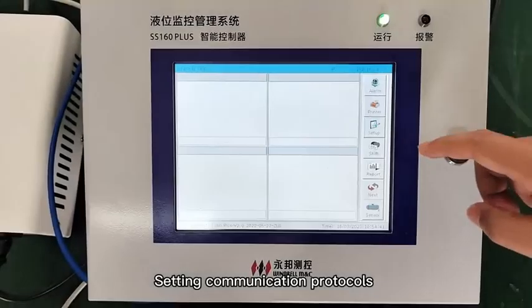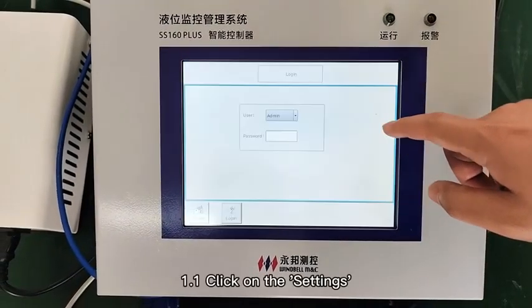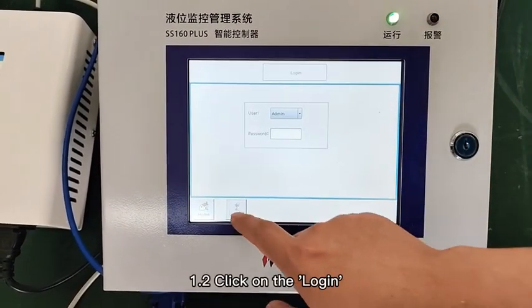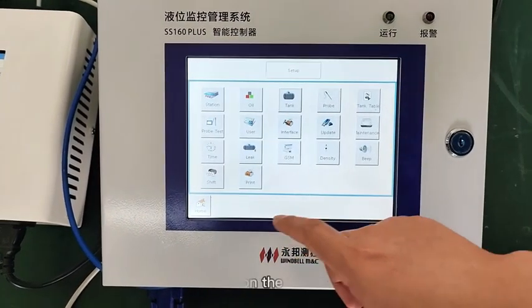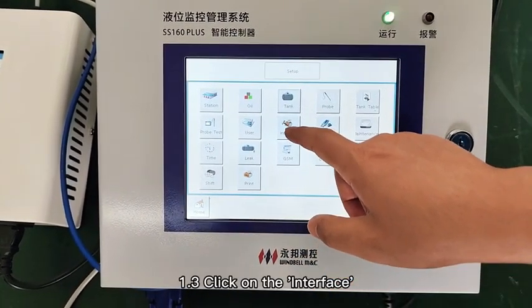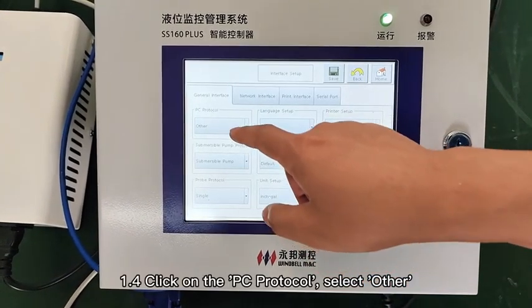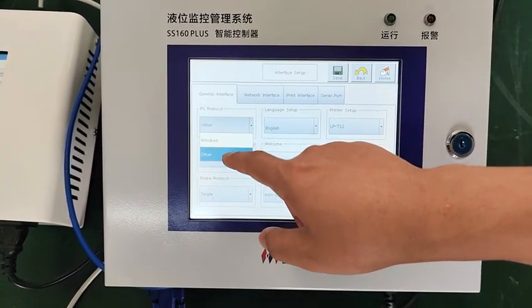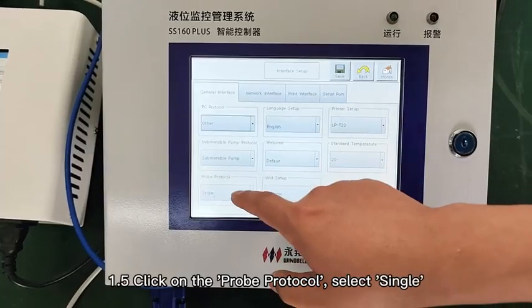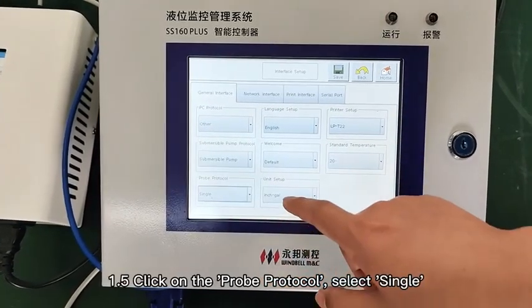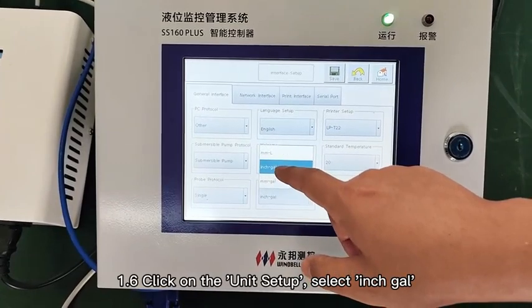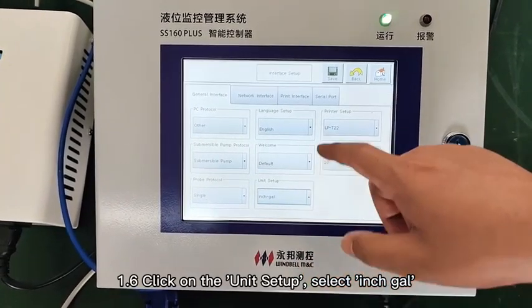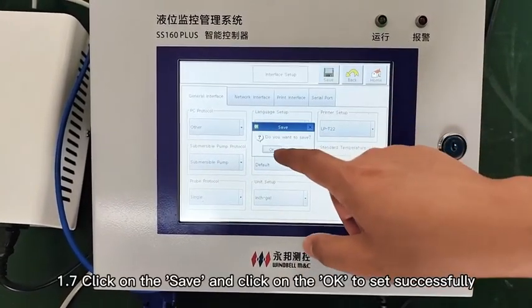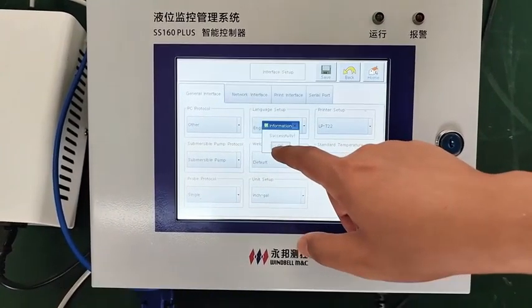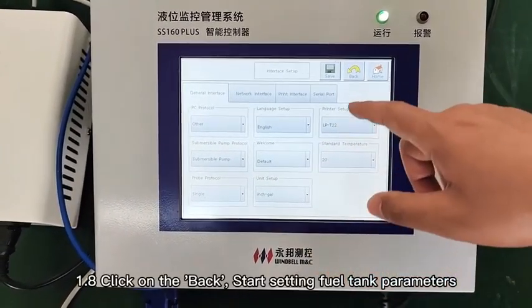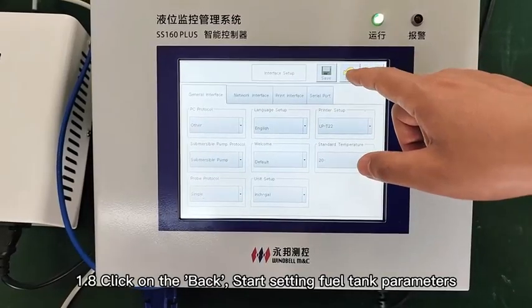Setting communication protocols. 1. First, click on Settings, then click on Login. 3. Click on Interface. 4. Click on PC protocol, select Other. 5. Click on probe protocol, select Single. 6. Click on unit setup, select inch/gal. 7. Click Save and then click OK to set successfully. 8. Click on Back, start setting fuel tank parameters.